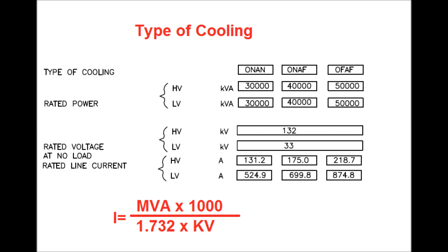For 40 MVA, the HV side current is 175 A and the LV side current is 699.8 A. For 50 MVA, the rated line current is 218.7 A on the HV side and 874.8 A on the LV side. These are the full load rated currents on the HV side and LV side.